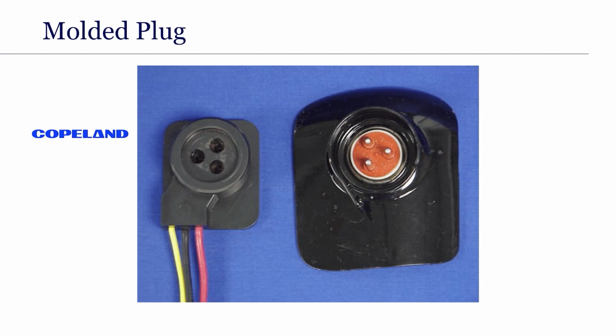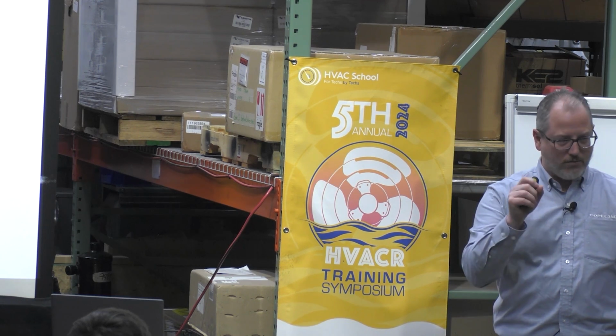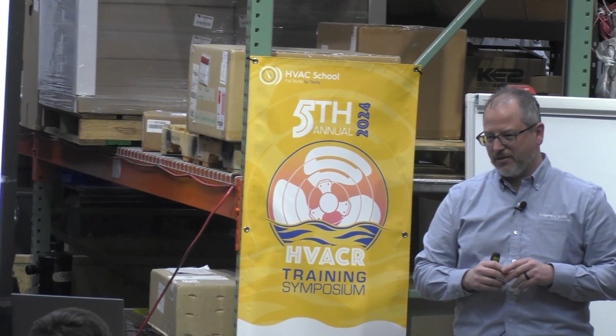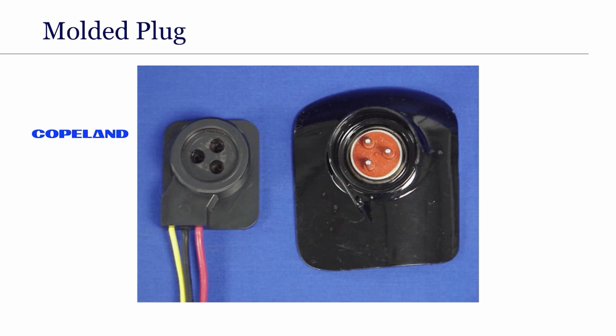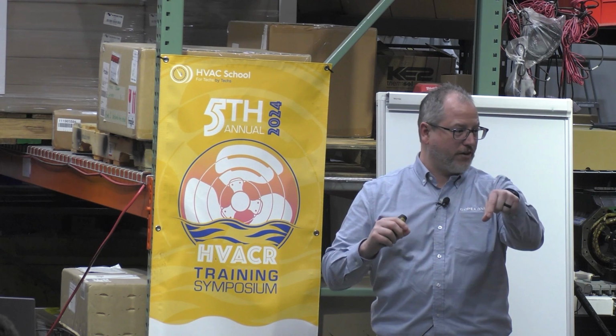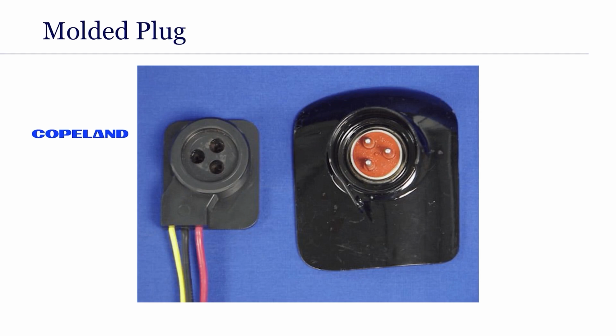Okay? And then with the molded plugs, never pull that molded plug out when you're standing right in front of the compressor, facing it. All right? If there's gas in there, I was doing a training somewhere, and somebody was telling me they were watching some OEM do this live video, and the person was right in front of the unit and pulled off that plug, and there was refrigerant in the system, and the pin in the fusite let go. And the pin hit the guy, and refrigerant went flying all over the place. So don't do that. That's very dangerous. So always stand to the side when you're pulling that plug out. It's something that people don't really think about, but be careful.